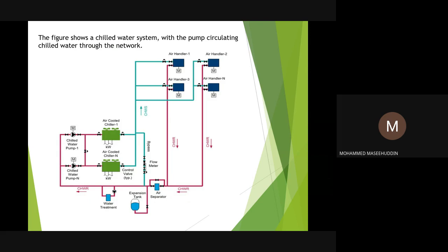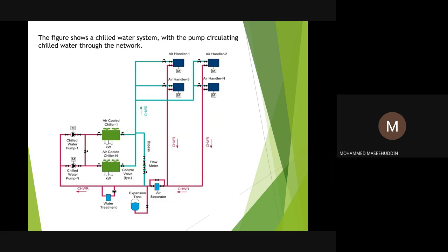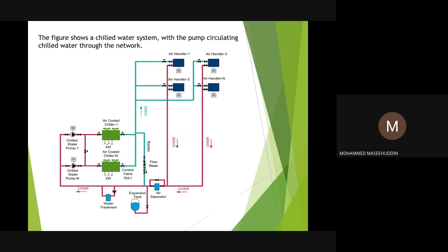This is a typical layout of how the chill water system, which includes the chill water pumps, works in the building. If you look at the drawing, there are basically two chill water pumps, chill water pump 1 and chill water pump N, which throw the water to two chillers, chiller 1 and chiller N. The green lines indicate the supply side, supplying the chill water from the chillers to different AHUs here, but it could be FCUs, fan coil units, as well.